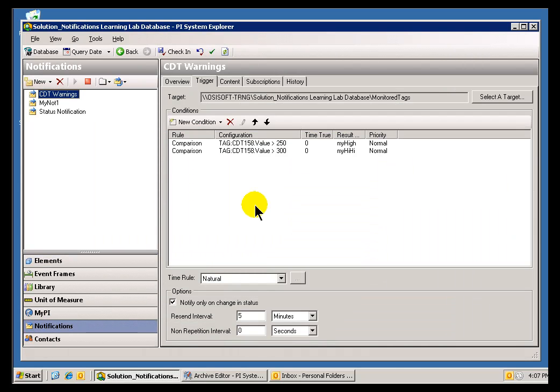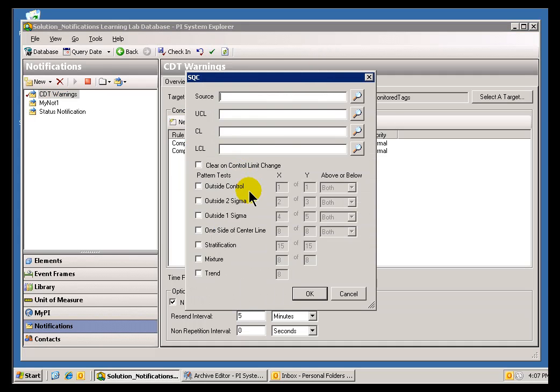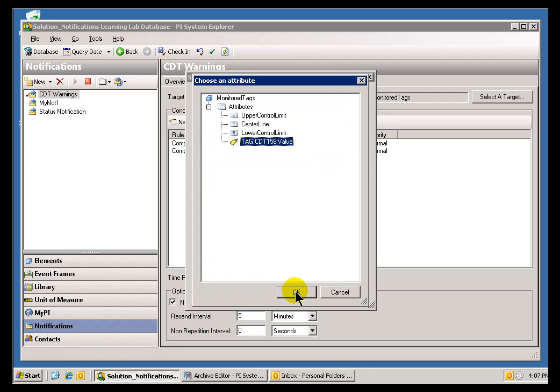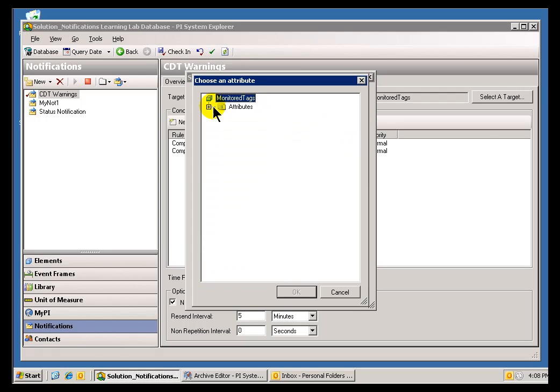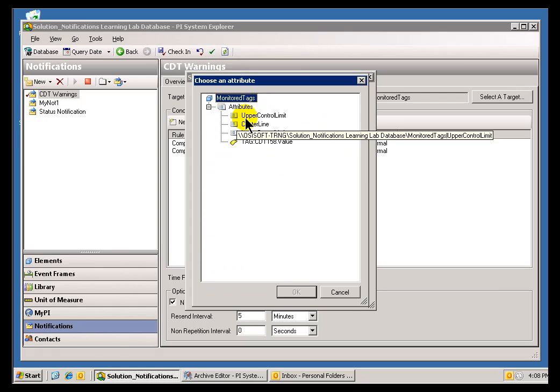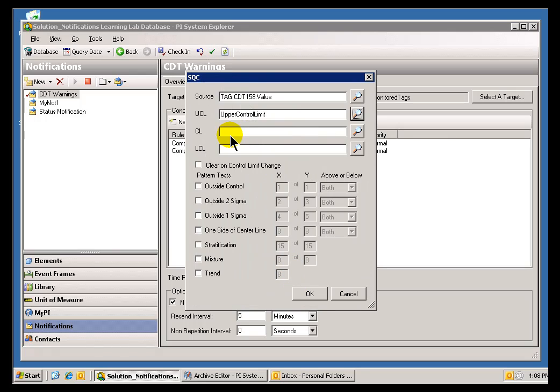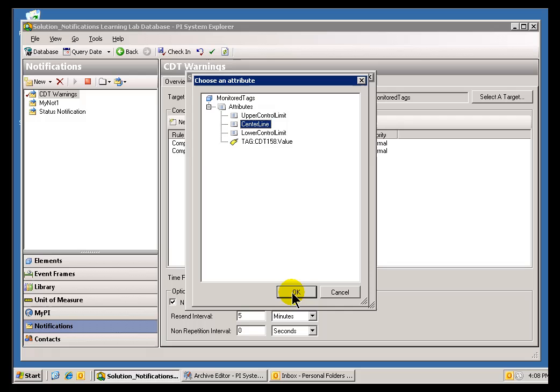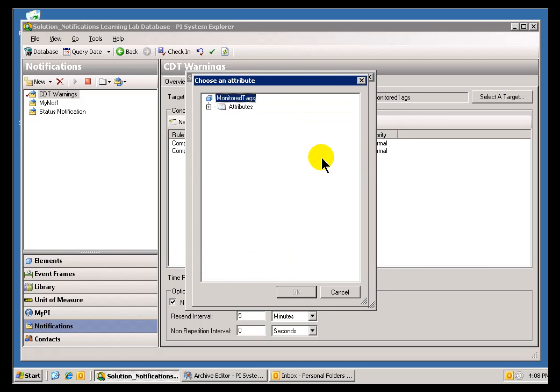In here, under Notifications, let me go ahead and add not a whole new Notification, let's just add a condition to this. We'll do an SQC Alarm. That's the Source Tag we're interested in tracking. And for our Upper Control Limit, Center Line, etc., we're going to use those things we just defined over in this same Element called Monitor Tags.